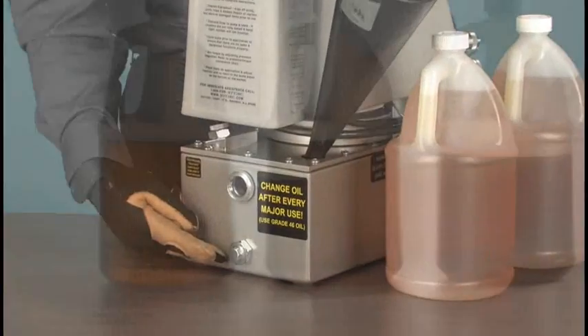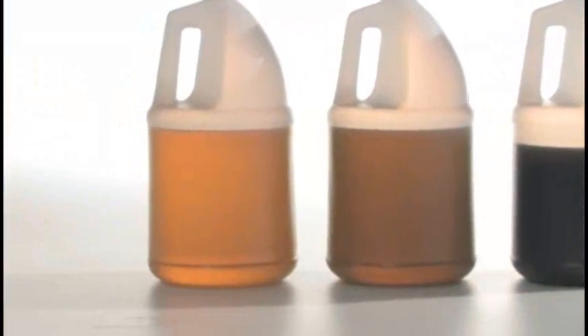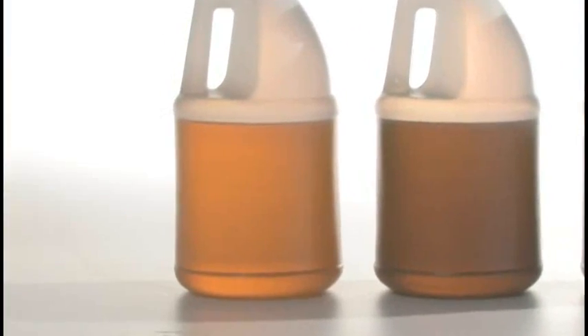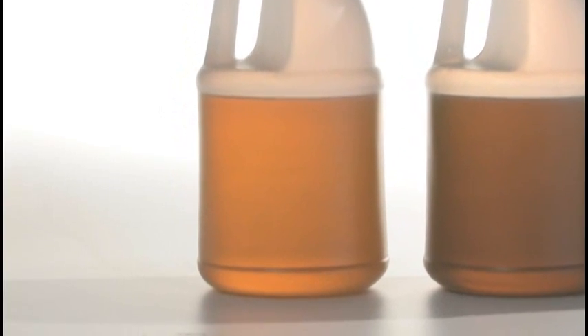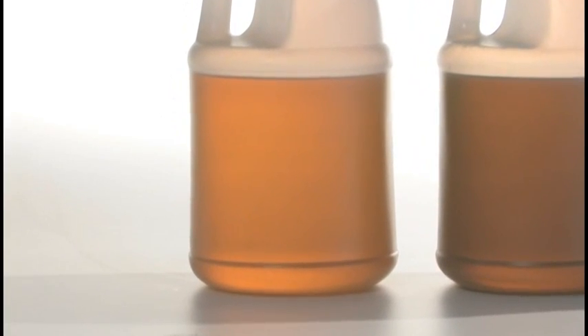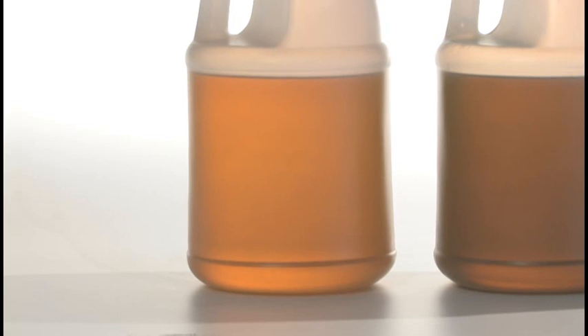A drain plug is provided. Oil should be changed after about 40 to 60 hours of run time depending on continuous use, temperatures, and dusty or humid environments.